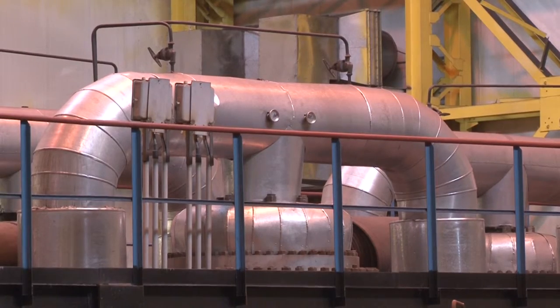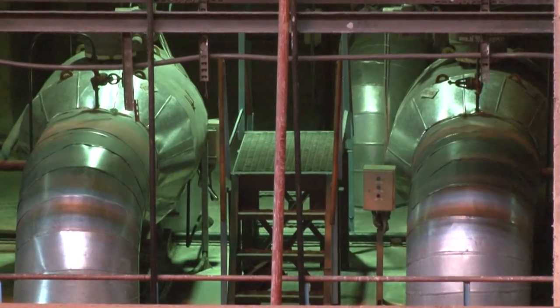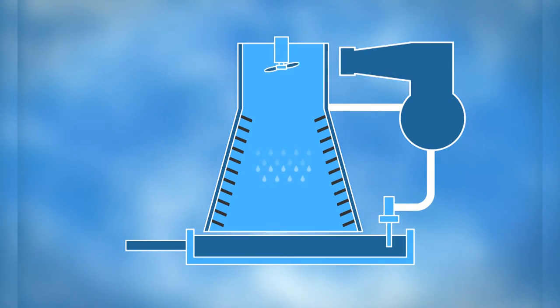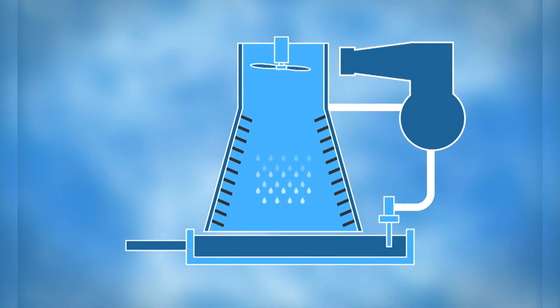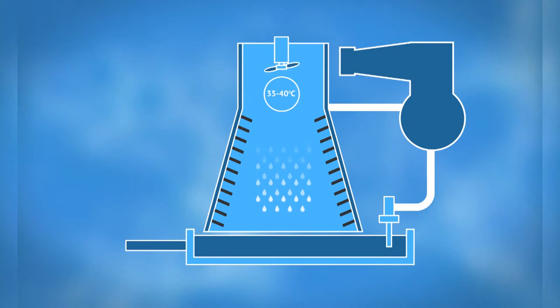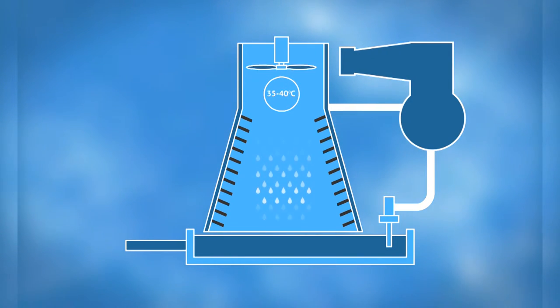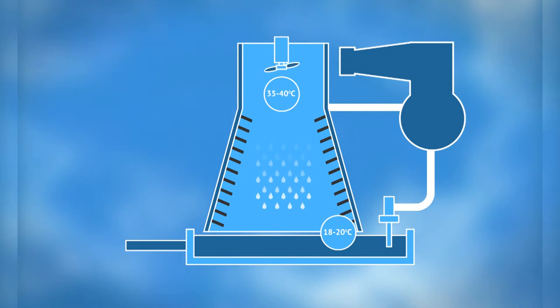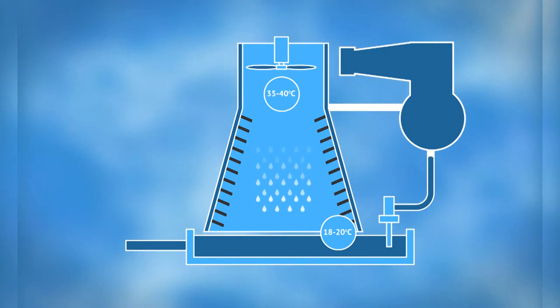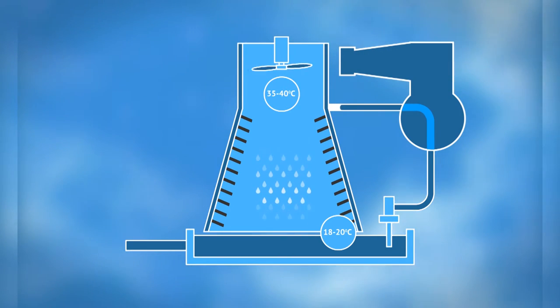Water used in the turbine cooling process is delivered to the cooling tower — a device for cooling water using an atmospheric air stream. Water with a temperature of 35 to 40 degrees Celsius enters the tower, which has a ventilator installed causing constant motion of the water drops. While dripping back along the walls of the tower, the water cools off to a temperature of 18 to 20 degrees, and is then returned to the process of cooling the excess steam in the condenser.